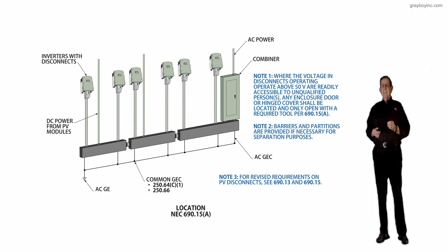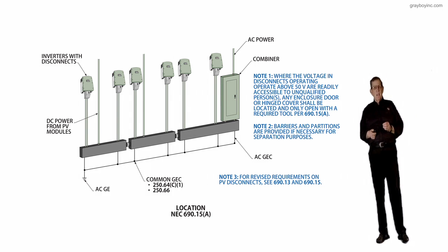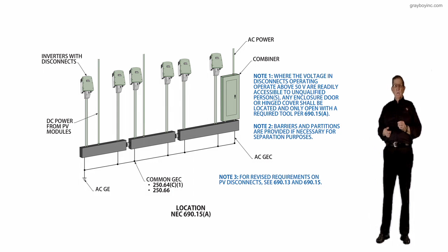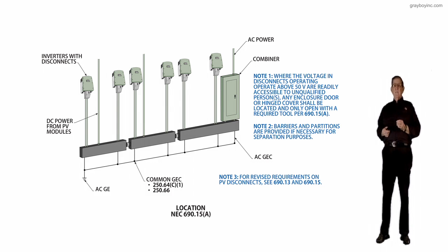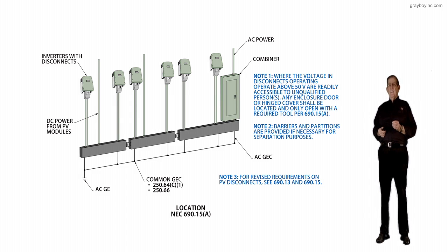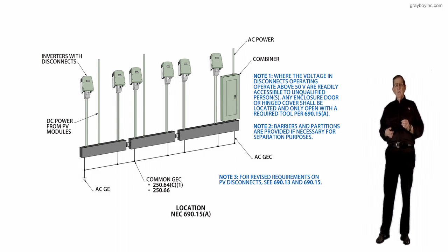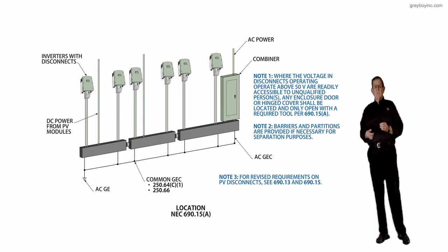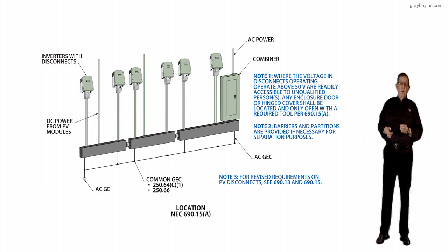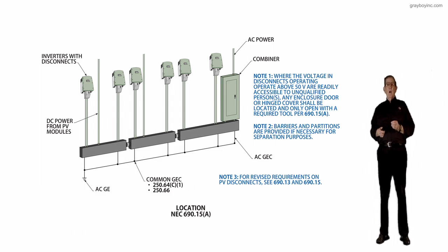An open disconnect enclosure contains wiring and terminals that can be touched with tools, probes, or even the hands. There is a need to require, as a minimum, a tool to physically open these enclosures. The voltage level of 50 volts is consistent with other Article 690 requirements.